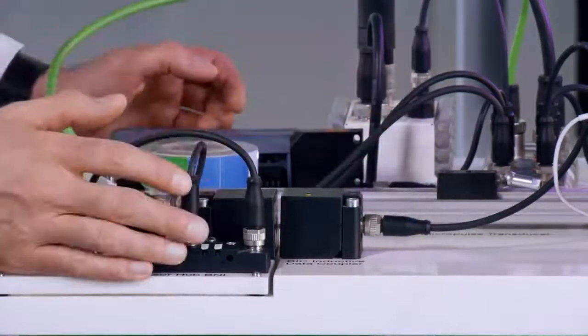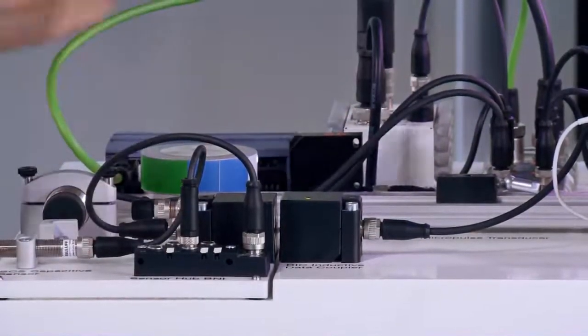Why? When IO-Link was born, the people responsible for creating this type of interface decided that IO-Link would use the simplest, the cheapest cable available in the world. Which one, Daniel? We are talking about the 3-wire basic cable, which is widely used to connect simple binary sensors, very often using the common M12 connector to make the connection very easy and very fast.